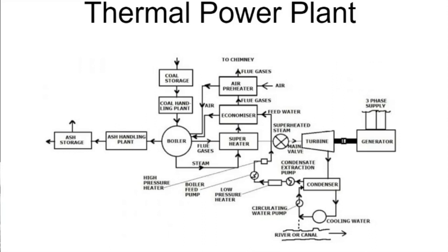discuss another 3 important disadvantages of thermal power plant. The one is that the starting time required is so much high. मतलब अगर आपने थर्मल पावर प्लांट को गलती से बंद कर दिया और आपको लगता है कि हमें एक बार उसको चालू करना है, तो वो ऐसे नहीं होता है कि जैसे आपने बटन दबाया और ऊपर का फैन चालू हो गया। इसको चालू होने में मिनिमम 6 से 8 घंटा लगता है in the cold condition.